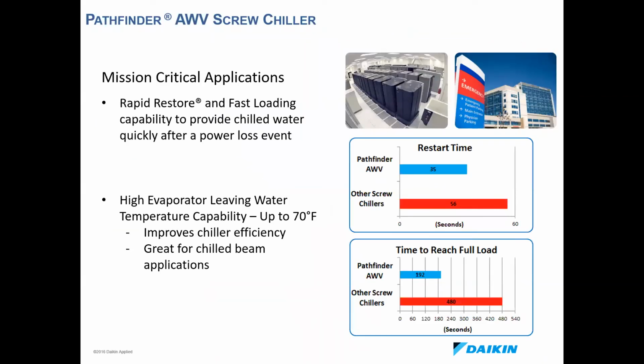Just a quick note on mission critical applications for AWV. AWV and AGZ are both good applications for mission critical, but what makes it extra beneficial is the rapid restore and fast loading. Our times are about half of that of our competitors. What the AWV controller is doing in a rapid restore or fast loading scenario is skipping the less important startup checklist items so that it can get the chiller online faster in the event of a power outage or power surge. So you can get that chiller back online and get that process or that building cooling load satisfied faster after a power event.